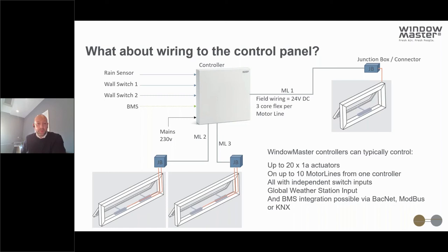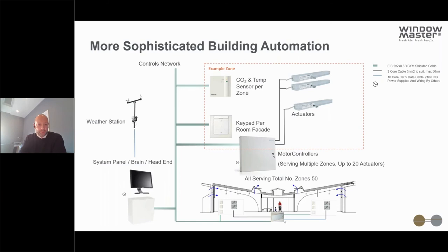Our MotorLink controllers are network enabled and can be easily integrated into the BMS via BACnet, Modbus, or KNX. In the biggest smart buildings, the overall system is much more sophisticated — controllers sit on a controls network with a system panel or head end monitoring each zone using sensors in the spaces and optimising window positions in each group according to ventilation demand and weather conditions.